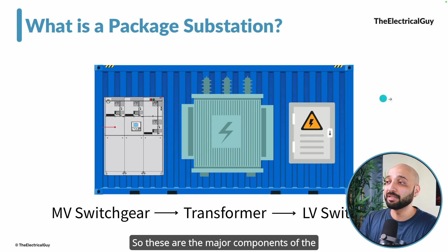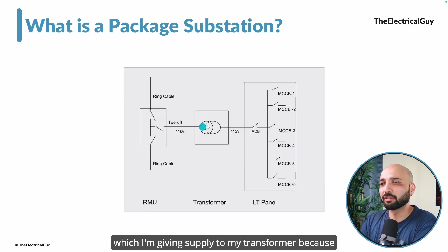So these are the major components of the package substation. If you look at this simplified diagram, this gives a better idea. Here we have the RMU section with load break switch 1 and load break switch 2, which connect my distribution network, ringmain distribution network, and this will be my circuit breaker through which I give supply to my transformer, because I want to protect my transformer.